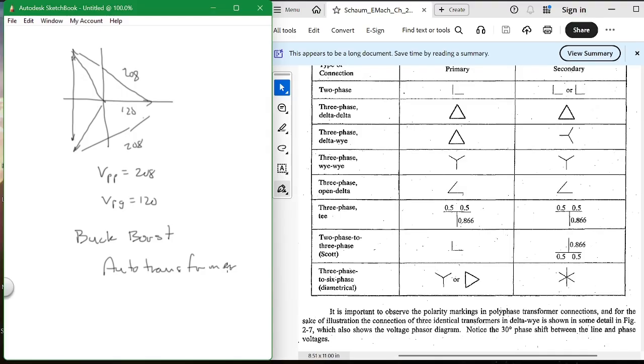Is this an inverter or something that will work on 208, or do you have to go to whatever? Usually most things will work on either 208 or 240, but you have to be very careful. You've got to watch and see whether it'll work on 208. If it does, you're good to go. If it doesn't, you have to do something about it, and a buck boost transformer, an auto transformer, will do that.